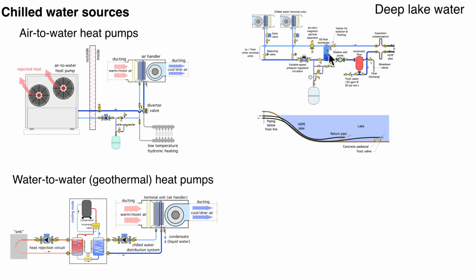It's a pretty simple idea. I would tell you as a very first step, check any environmental regulations before you think about this. Today, it's not simply a matter of dropping a pipe into a lake, even if you own the property and the shoreline. There may be procedures or qualifications to do that. Assuming that that is a hurdle you can cross, it's a viable system. Now, the other side of the heat exchanger, of course, isolates the lake water from the balance of the system. In this case, it's a variable speed circulator, and it could be multiple air handlers, each with a zone valve. So as these zone valves open and close, the circulator would change speed, and you would trim out that system with air and dirt and magnetic particle separation. It has its own expansion tank. Basically, the left side of that heat exchanger is a closed loop system, whereas the right side is an open loop system back out to the lake.